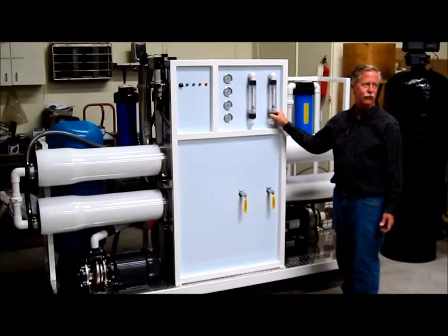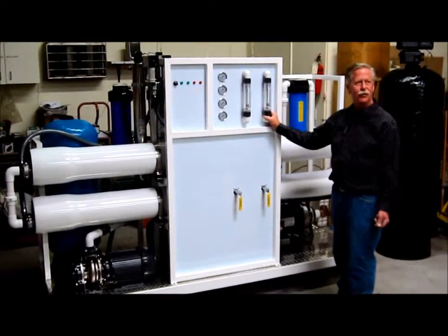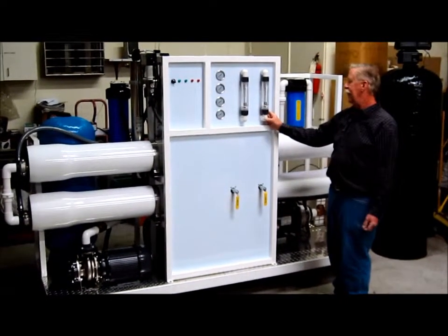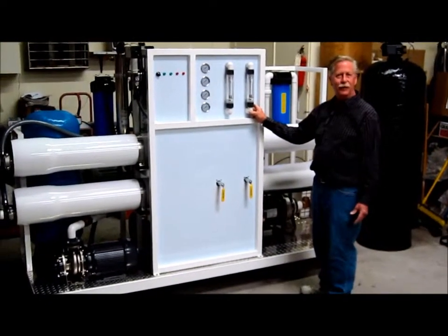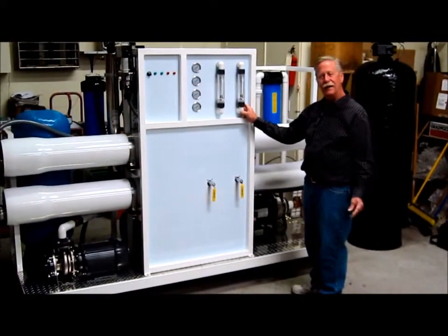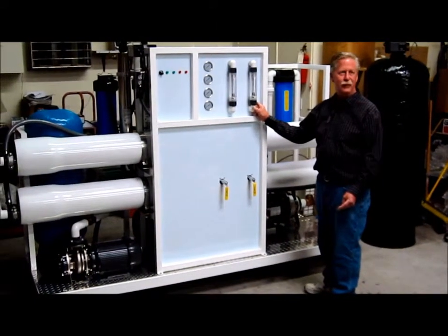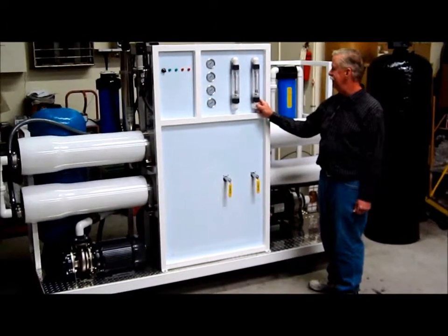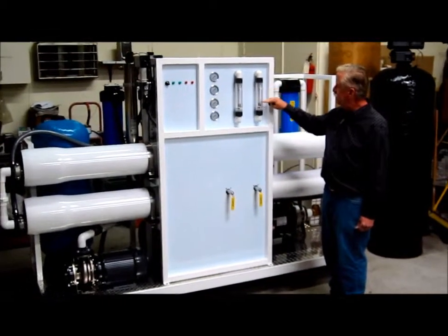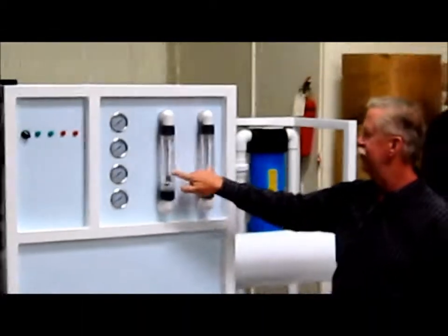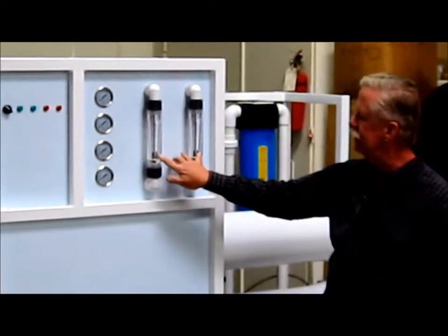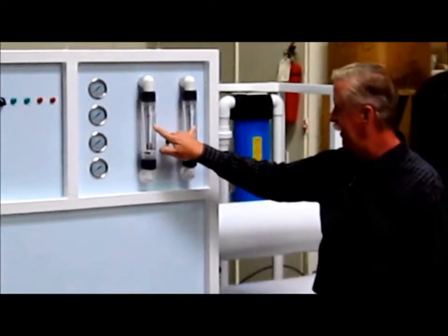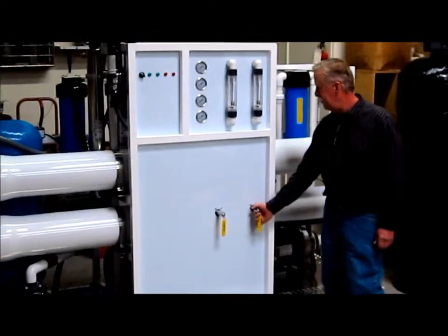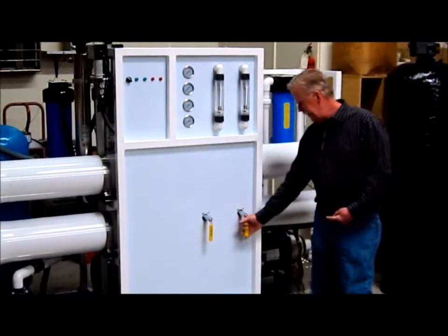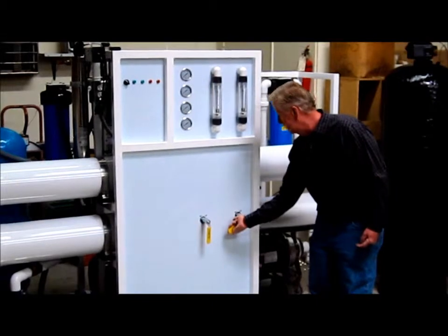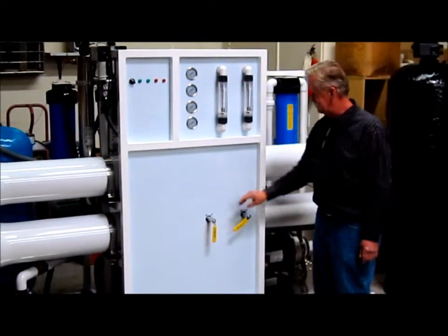Now with reverse osmosis, it typically takes 2 gallons to make 1 gallon. That is because you have to take the contaminants that are in the water and take them away from the membrane to keep the membrane from getting clogged up, because it is a very fine filter. So this tells you how to balance the system. In other words, what you want to do is have these two floats in here at the same level. Now the floats are controlled by how much water is going to the drain through the valves here. So you would turn this until you got these balanced.